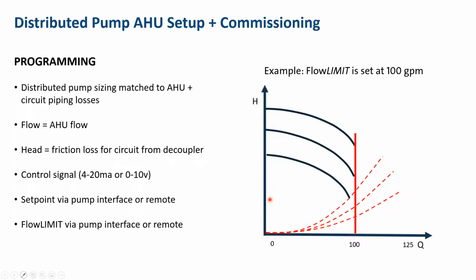And then lastly is a parameter within our pump itself called flow limit. So that would be another settable parameter which would equal what the max flow rate is for that terminal unit, in this case an air handler. So we wouldn't need an additional flow limiting device or anything like that to make sure that we don't overflow the coil. That would all be done electronically.